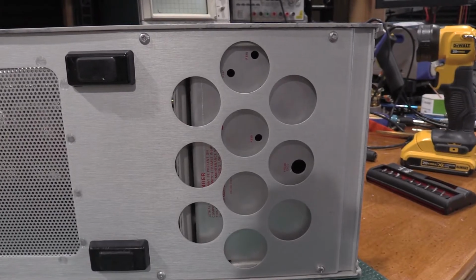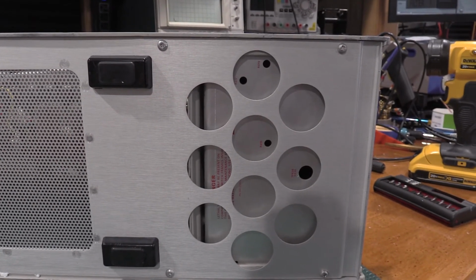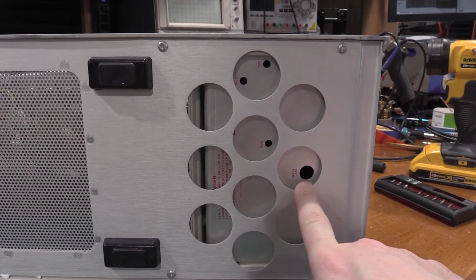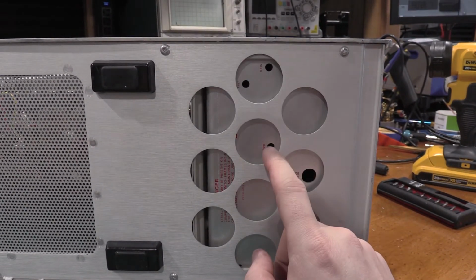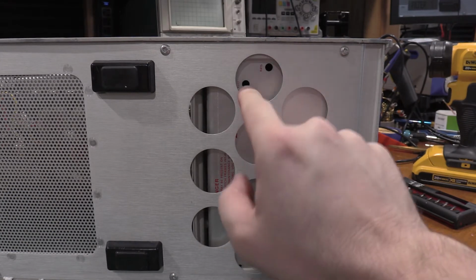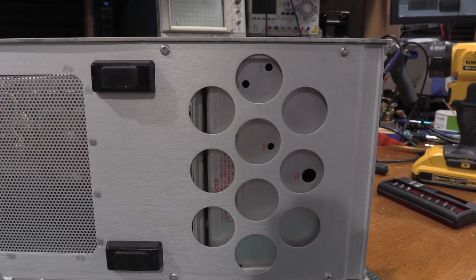Okay, to do a 177 properly, the unit does need to be on its side. There's a plug you need to remove in this hole, and then we have 3 adjustment points. So not much to do on a 177, but very important because it'll throw off the calibration for the rest of the unit. So let me get the service manual, and we'll get to it.